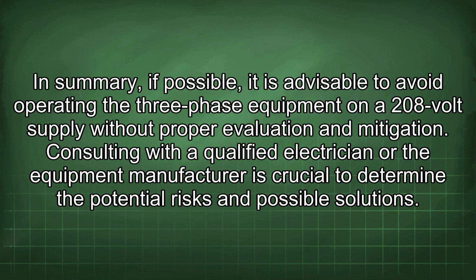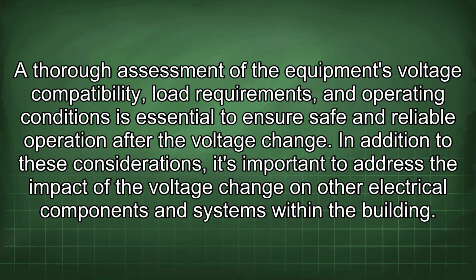In summary, if possible, it is advisable to avoid operating the three-phase equipment on a 208-volt supply without proper evaluation and mitigation. Consulting with a qualified electrician or the equipment manufacturer is crucial to determine the potential risks and possible solutions. A thorough assessment of the equipment's voltage compatibility, load requirements, and operating conditions is essential to ensure safe and reliable operation after the voltage change.